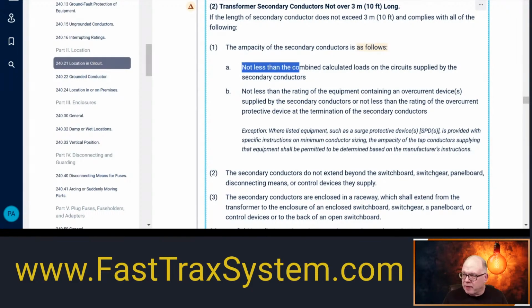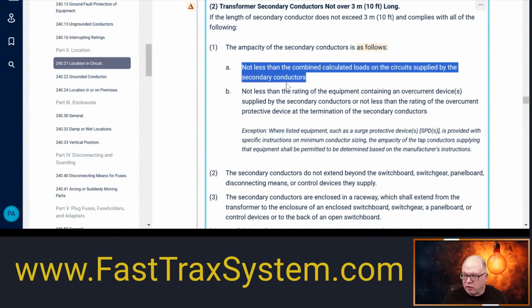Not less than the combined calculated load on the circuit supplied by the secondary conductors. So, first, from our design's perspective, we have to know what the loads are. We could have a transformer that's feeding 2 separate panels that each would be, let's say, 100 amps. Then whatever's being supplied by each of those panels is going to be the combined load, and the actual conductor can't be less than that. This is a minimum rule: not less than.